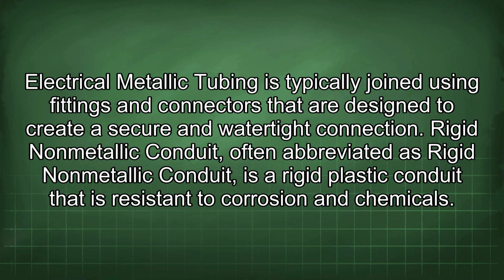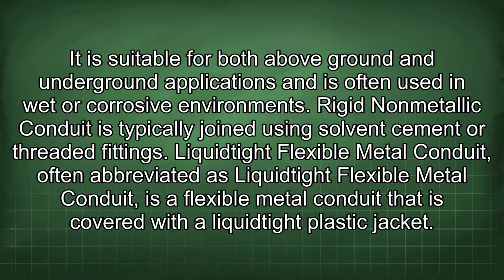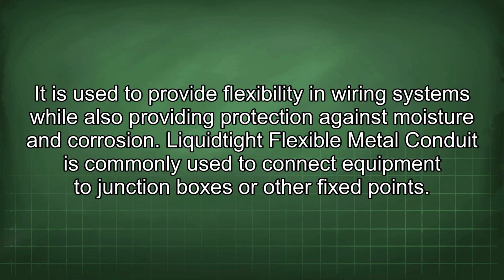Rigid non-metallic conduit, often abbreviated as RNC, is a rigid plastic conduit that is resistant to corrosion and chemicals. It is suitable for both above-ground and underground applications and is often used in wet or corrosive environments. Rigid non-metallic conduit is typically joined using solvent cement or threaded fittings. Liquid-tight flexible metal conduit, often abbreviated as LFMC, is a flexible metal conduit that is covered with a liquid-tight plastic jacket. It is used to provide flexibility in wiring systems while also providing protection against moisture and corrosion. Liquid-tight flexible metal conduit is commonly used to connect equipment to junction boxes or other fixed points.